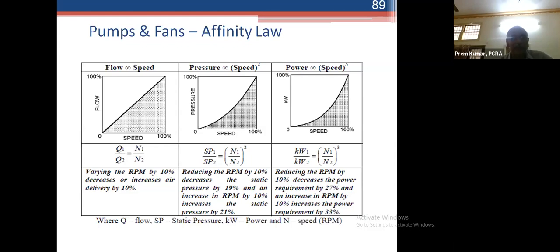If you reduce speed by 10%, your flow will get reduced by 10%, whereas the pressure will get reduced by 19%. Power will get reduced by 27%, cube law. So this is applicable only for centrifugal equipment. The centrifugal compressor, centrifugal pump, centrifugal fan, it is applicable. This is not applicable for axial. Okay.